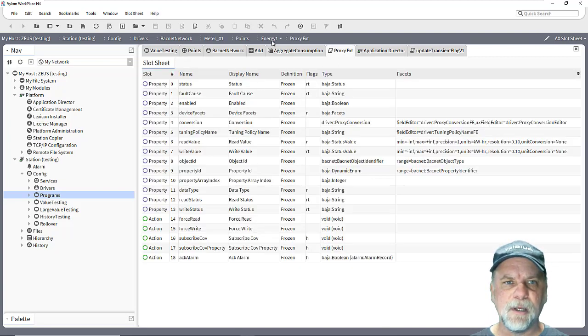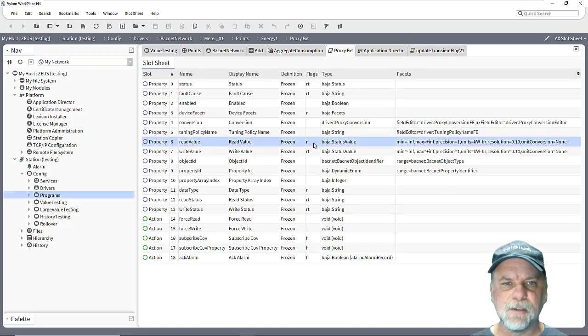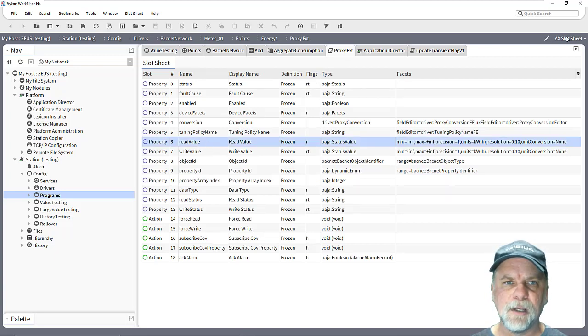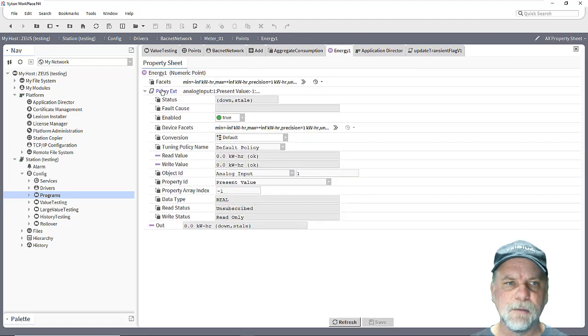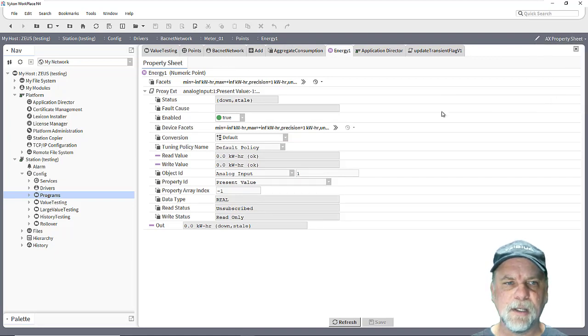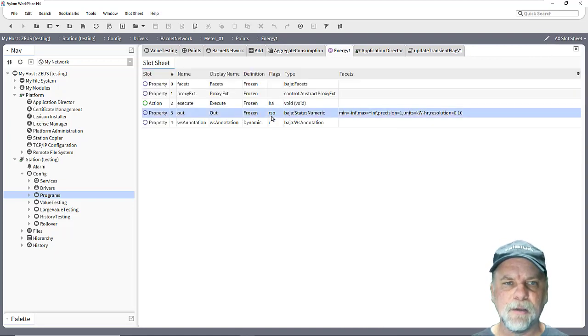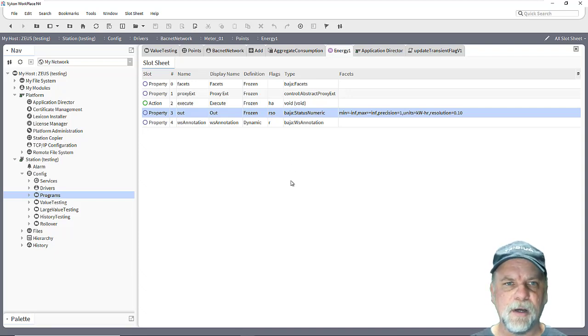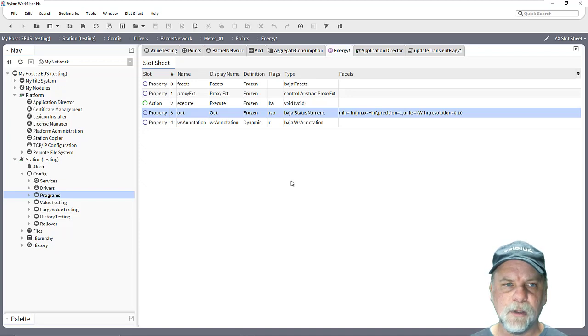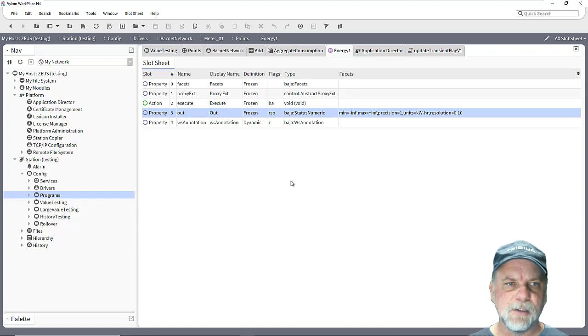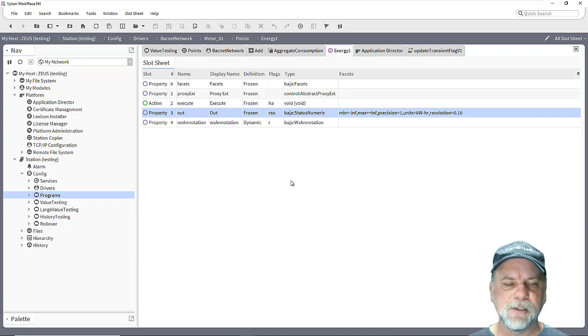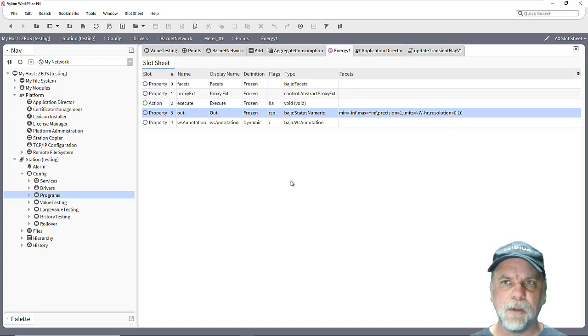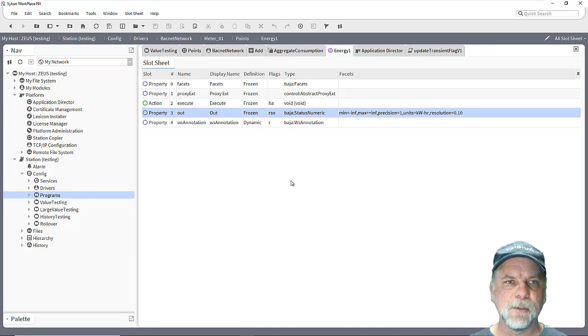So this is the energy one proxy extension and you can see the transient flag is cleared from the read value slot. And if I look at the property sheet of the energy one point and look at the slot sheet here, again the transient flag is cleared. So those values will be saved persistently to the bog file. When the station restarts it'll load the last known value, and that's a good process to use with control points that are totalized and are persistent in the field device, so that we can maintain the last known value which can help with our control logic as far as aggregating values together and things of that nature, or some other kind of control logic that we're using.